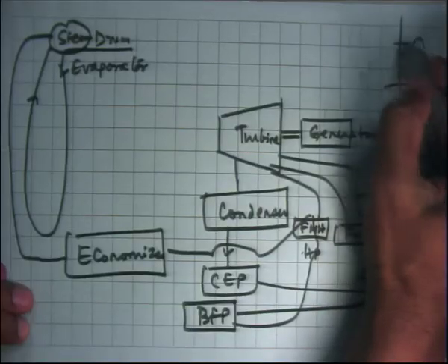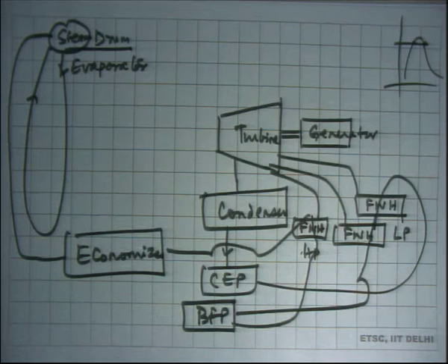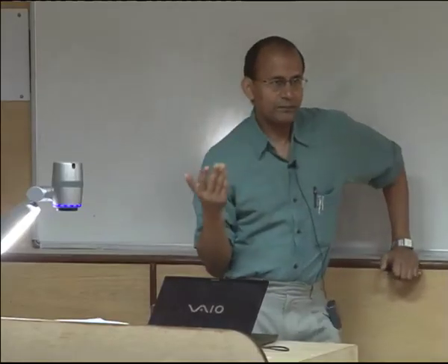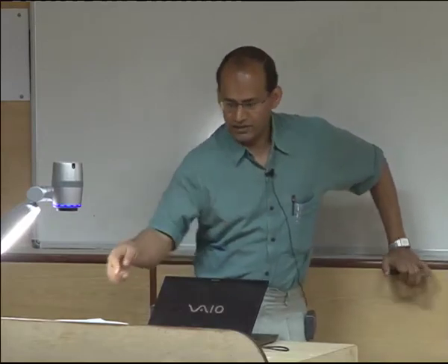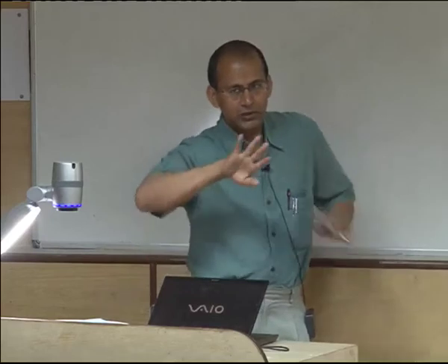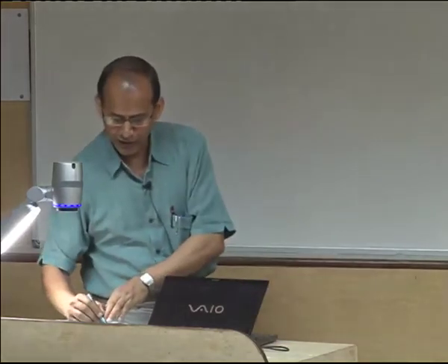because at that high pressure, if you look at the PV diagram, at that high pressure Vf and Vg start getting closer to each other. Okay, so the density of the liquid and the density of vapor are not substantially different. So, if you just use gravity, separating them out is going to be increasingly difficult as you get closer to the critical point. Okay, so you use gravity and other additional measures in the steam drum to separate the liquid and vapor. Then the vapor from there goes back to the boiler superheater.